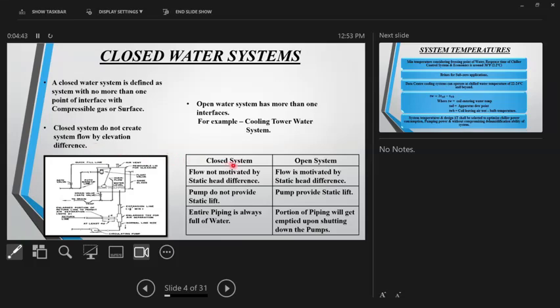A few of the differences in closed and open systems. In a closed system, the flow is not motivated by static head difference, as we saw. If the pump is running, then only the flow will get established. However, in open systems, the flow is motivated by static head difference. The difference is, if you switch off the pump of a cooling water system, some of the water in upper headers can get emptied even if your pump is not running, which means the flow can be and gets motivated by static head difference.